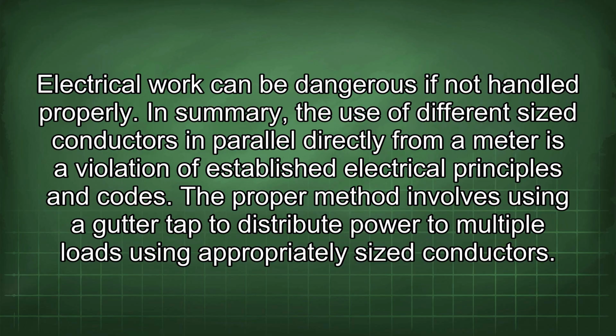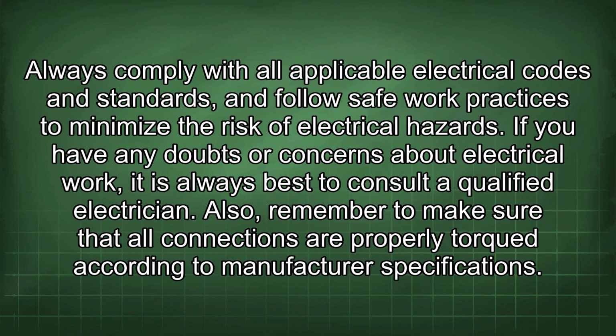In summary, the use of different sized conductors in parallel directly from a meter is a violation of established electrical principles and codes. The proper method involves using a gutter tap to distribute power to multiple loads using appropriately sized conductors. Always comply with all applicable electrical codes and standards, and follow safe work practices to minimize the risk of electrical hazards. If you have any doubts or concerns about electrical work, it is always best to consult a qualified electrician. Also, remember to make sure that all connections are properly torqued according to manufacturer specifications.